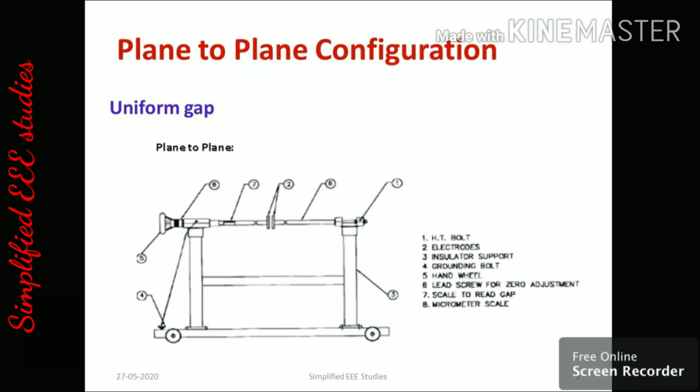Now you can turn off the supply and get into the room. Before touching any component, make sure that earthing has been completed successfully. Grounding should be done suitably. Thereafter, you have to maintain 20 mm. The gap distance between two plane electrodes should be 20 mm. Again, you can come out of the room. By using the supply side, you can maintain a suitable high voltage. Then you can observe when the spark or any other disturbance occurs.